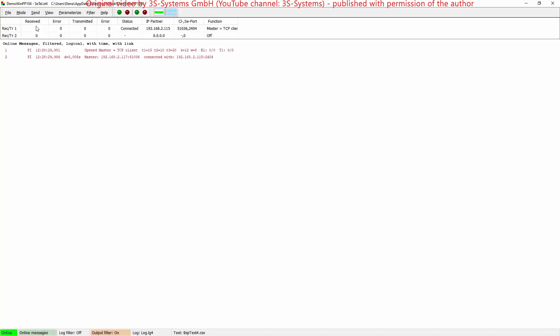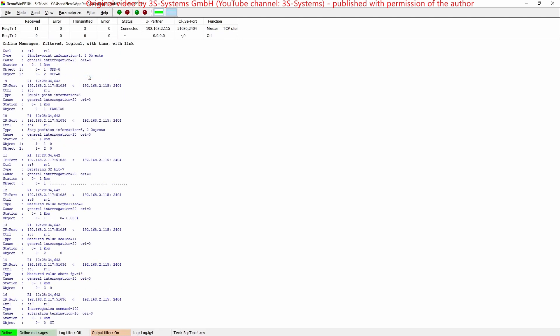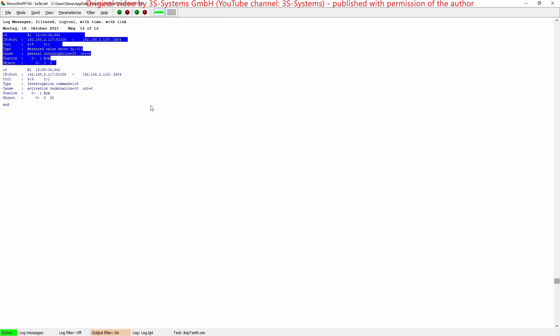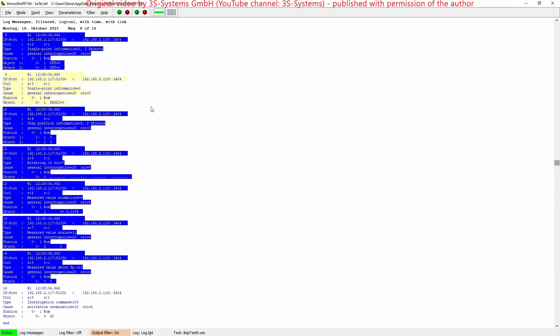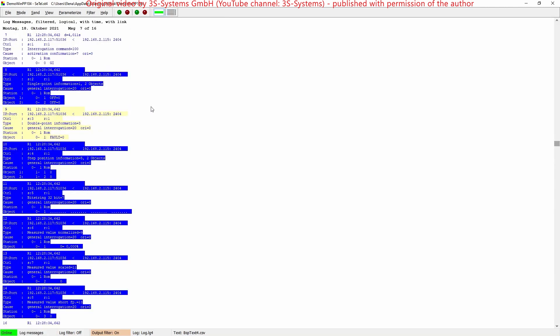If we now initiate a general interrogation from within a program like WinPP 104, we will receive the following messages from our IEC 60870-5-104 server, showing that all configured objects except the one excluded double-point information object are sent.